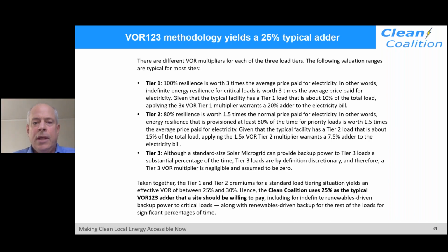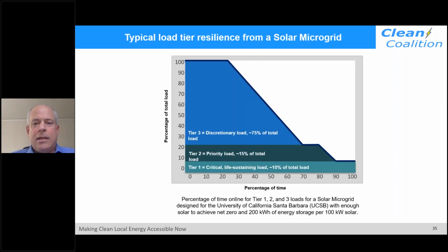This chart looks at the standard California solar microgrid scenario—the standard the Clean Coalition designs to. You size enough solar to net zero the site, and for every 100 kilowatts of solar you put in 200 kilowatt hours of energy storage.